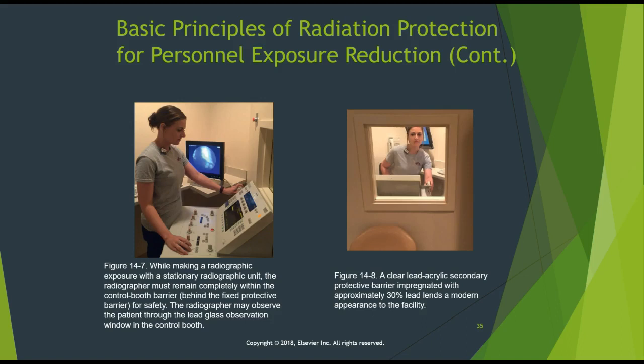And this is just some pictures. So this is your control area. This would be a secondary barrier. This is a secondary barrier with an impregnated lead window. Okay? And remember, the lead needs to be impregnated. Approximately 30% lead needs to be in that acrylic window.